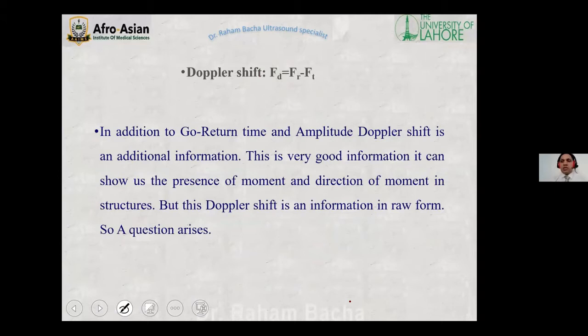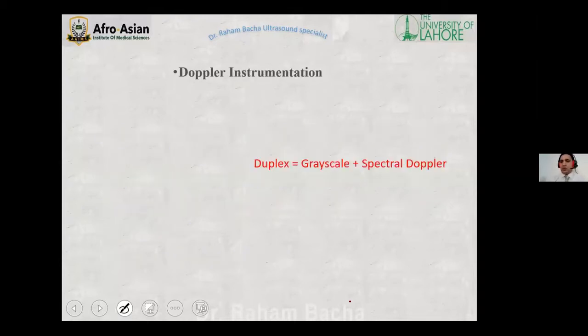Now this is a third type of information. Until now, we had only two types of information in grayscale sonography: one was go-return time and the other was amplitude. But now we have a third type of information, and that is Doppler shift frequency. This third type of information is very useful. It can give us information regarding the movement of the reflector: whether there is any movement or not, and if there is, what the direction of the movement is. That is very good information. But a question arises: how to present this Doppler shift? So instrumentation is needed for it.